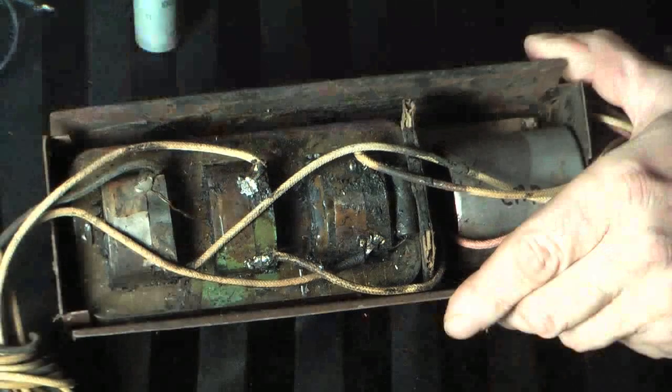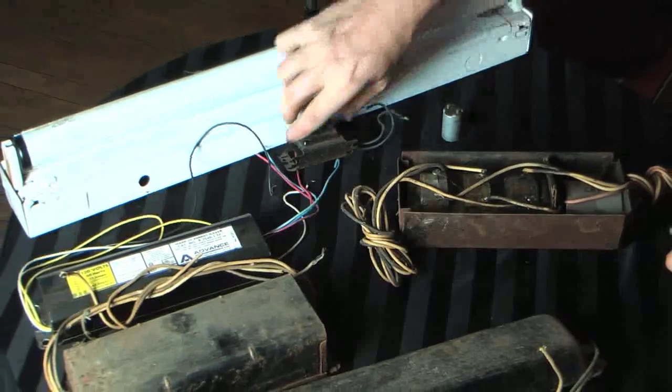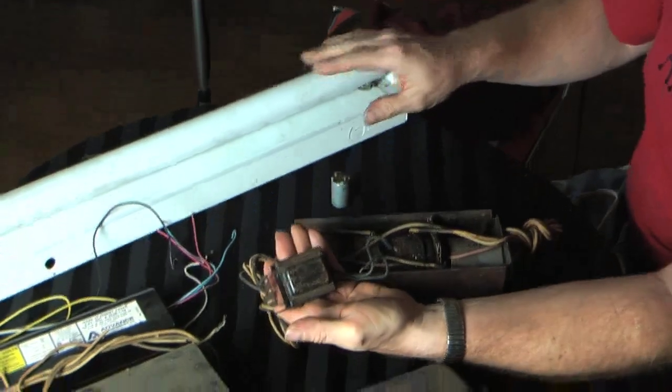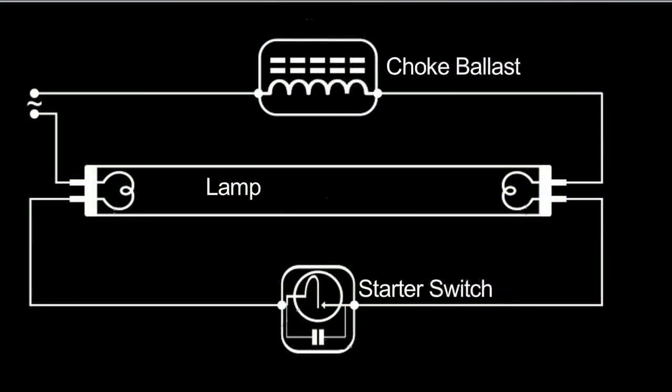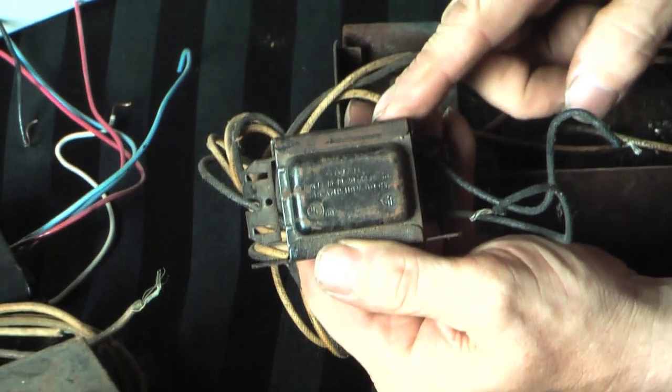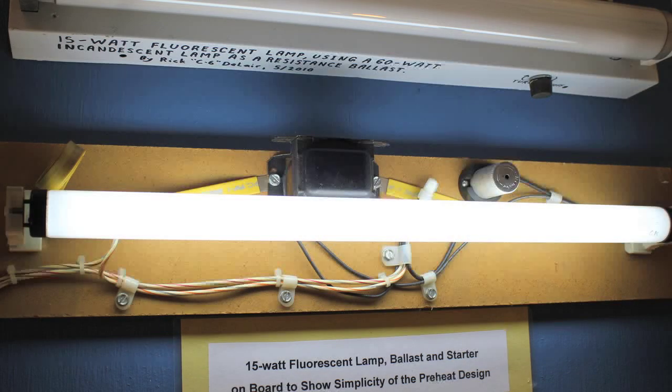So basically a ballast is a type of transformer combined with a current limiter. On the smaller fluorescents like this one, you have a simpler ballast. And this is it. This is what runs this lamp. It's a simple choke ballast, just like what's in the big ballast, except it doesn't need a step up transformer and it doesn't use a capacitor. So all it has is just a choke in series with the lamp. And this does everything. It limits the current to the lamp so it can't get too much current, it provides the inductive kick to start the lamp, and it limits the current through the cathodes during preheat. So this ballast does three things all in one little unit. And it's just a simple little coil with two wires in series with the lamp.